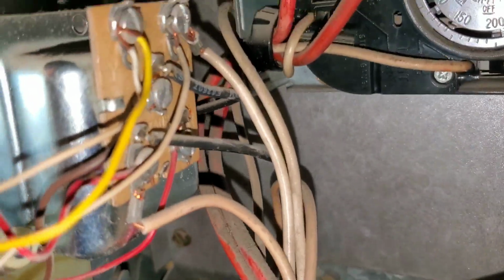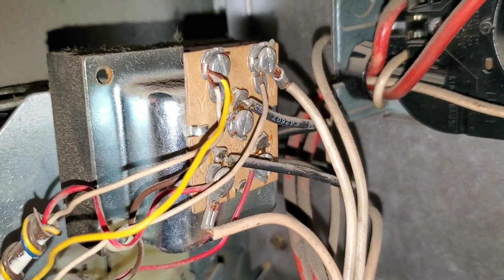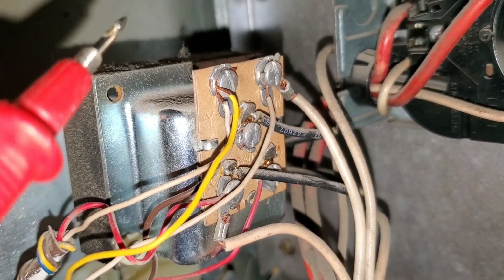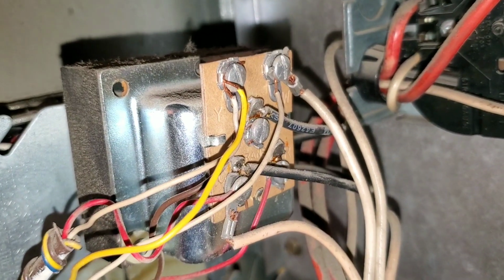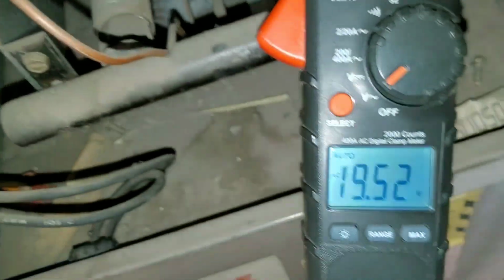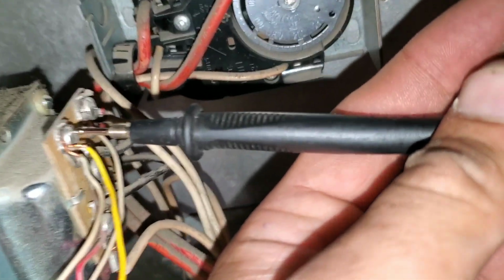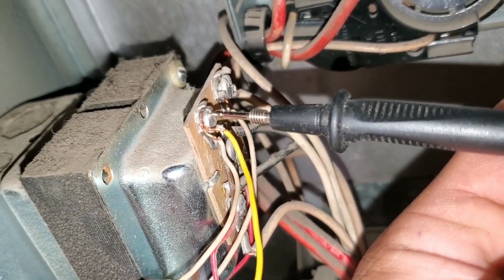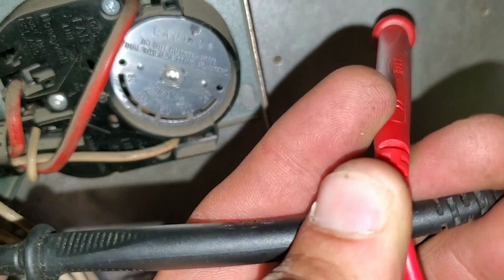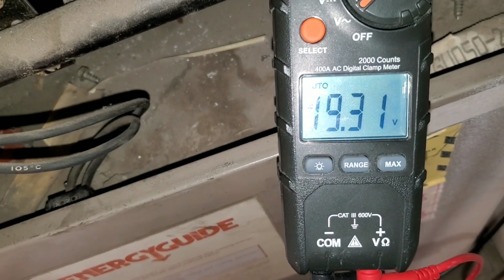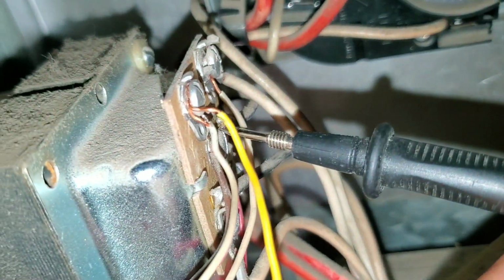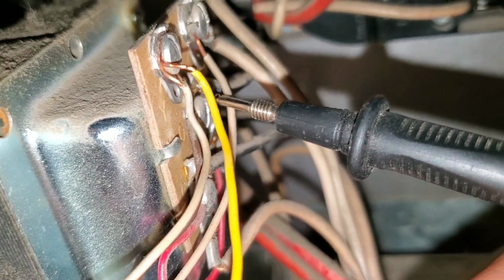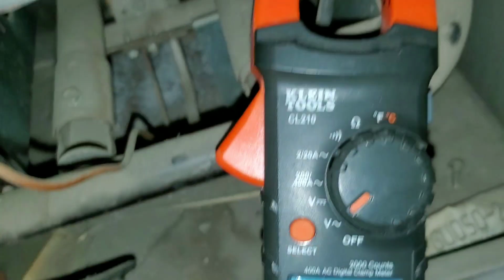What I'm going to do at this point is check my voltage here at the transformer. I'm going to check my voltage in my R, my Y, and my G terminal on my transformer. So here I have one of my leads on my R terminal at my transformer, and I'm putting one lead to ground, and I do have low voltage. Now we're going to check our Y terminal at the transformer, and you can see I have my lead on my Y, and here I have it to ground, and you can see that I do have low voltage. Here I have my multimeter set to volt AC. I have one of my leads on my G terminal on my transformer. I have my other lead to ground, and I do have low voltage.